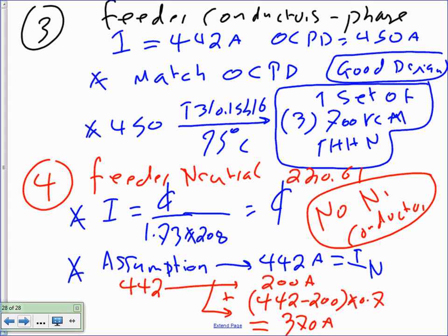370 amps, okay? Here's my amps for a neutral. If you want, which is a good idea, have a neutral on the panel just in case. But when I design, you guys will design a system. You look at all your mechanical equipment, not a single one of them has a neutral on it. There is no future neutral.